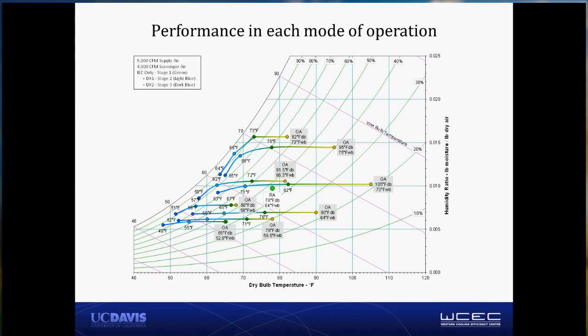You can see the way we've charted here. At each outside air condition, we're plotting the supply air condition. That's the net supply air condition, so what would actually be supplied to the space, including the fan heat, at each of the different modes of operation. So you can see at peak, 105 degrees, 73 degrees wet bulb. Indirect evap cooling on its own can drive the supply air down to about 82 degrees, and when you need additional cooling, you can turn on first stage of DX to get down to 71 or second stage to get down to 63.